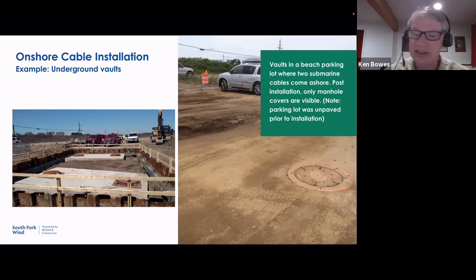That splicing process requires a climate-controlled atmosphere, almost like a clean room. They'll be placing plastic inside this concrete vault, and air handling equipment to both filter and condition the air to a certain temperature and humidity. That will take several days to set up and create an environment that is clean-room-like, operating-room-like, because we need to make sure no contaminants get into that cable splice.